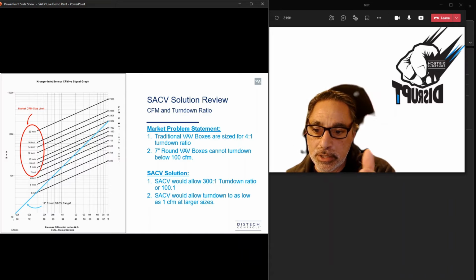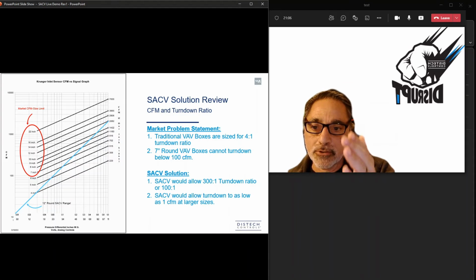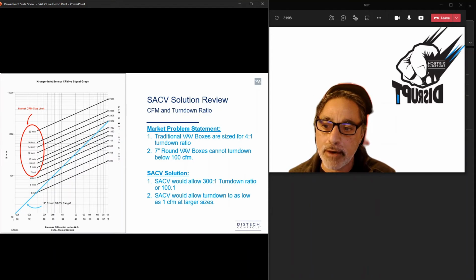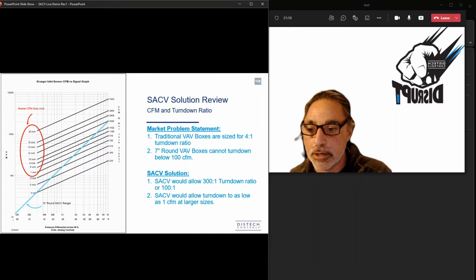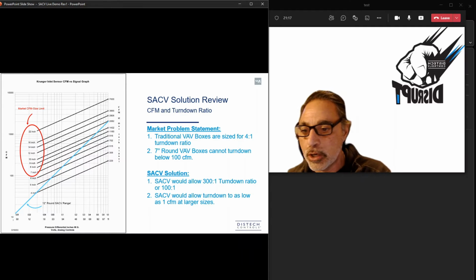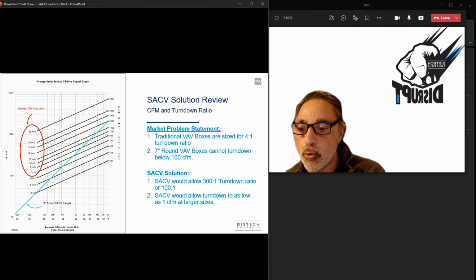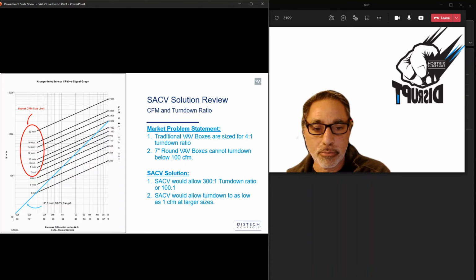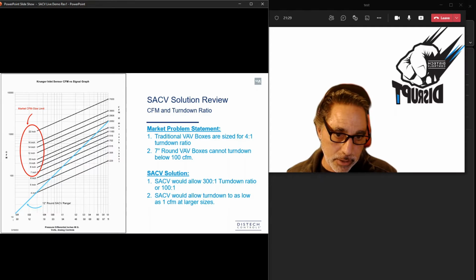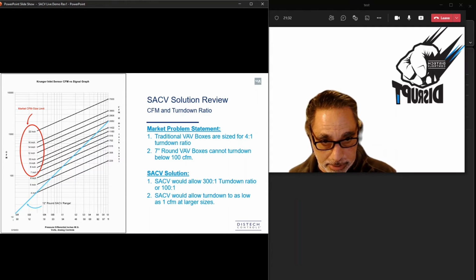And then you can see if you go down to the right, the range, from a pressure and then the amount of CFM. The reason you have that many sizes is to be able to get the accuracy in the amount of CFM that you would need in a space. What we're saying with this product, we could go down to 0.01 to 0.03 of pressure that you need within the space, and then we could go all the way up to over 2,000 CFM with only one product, which is a 12-inch round product.